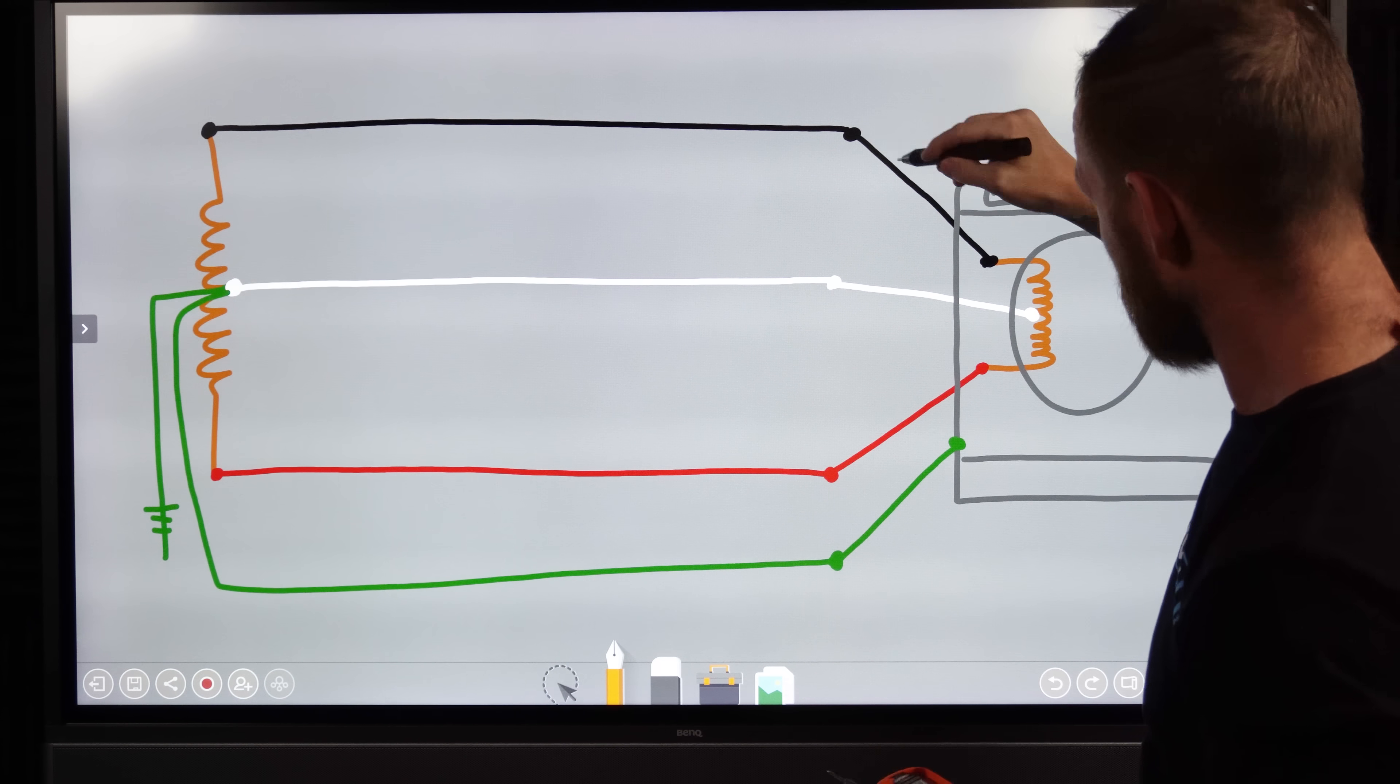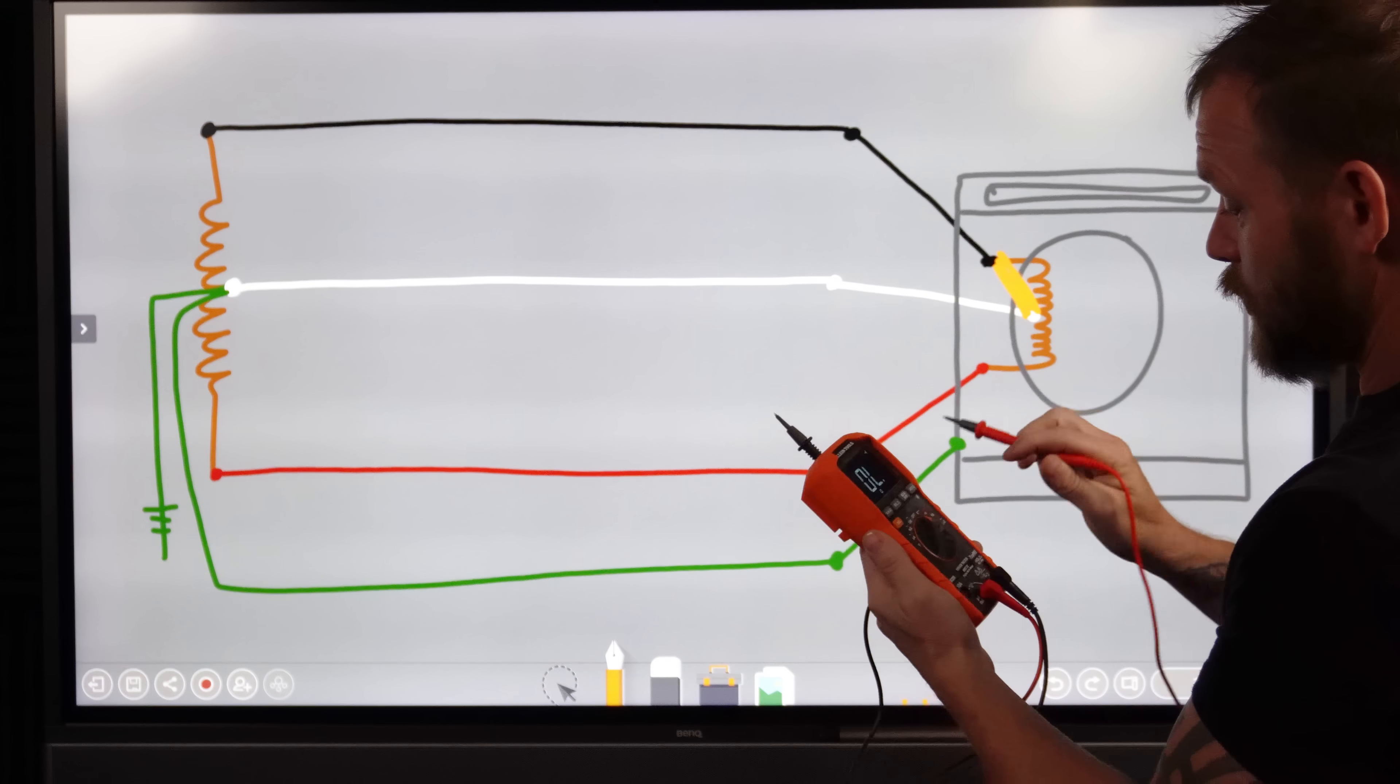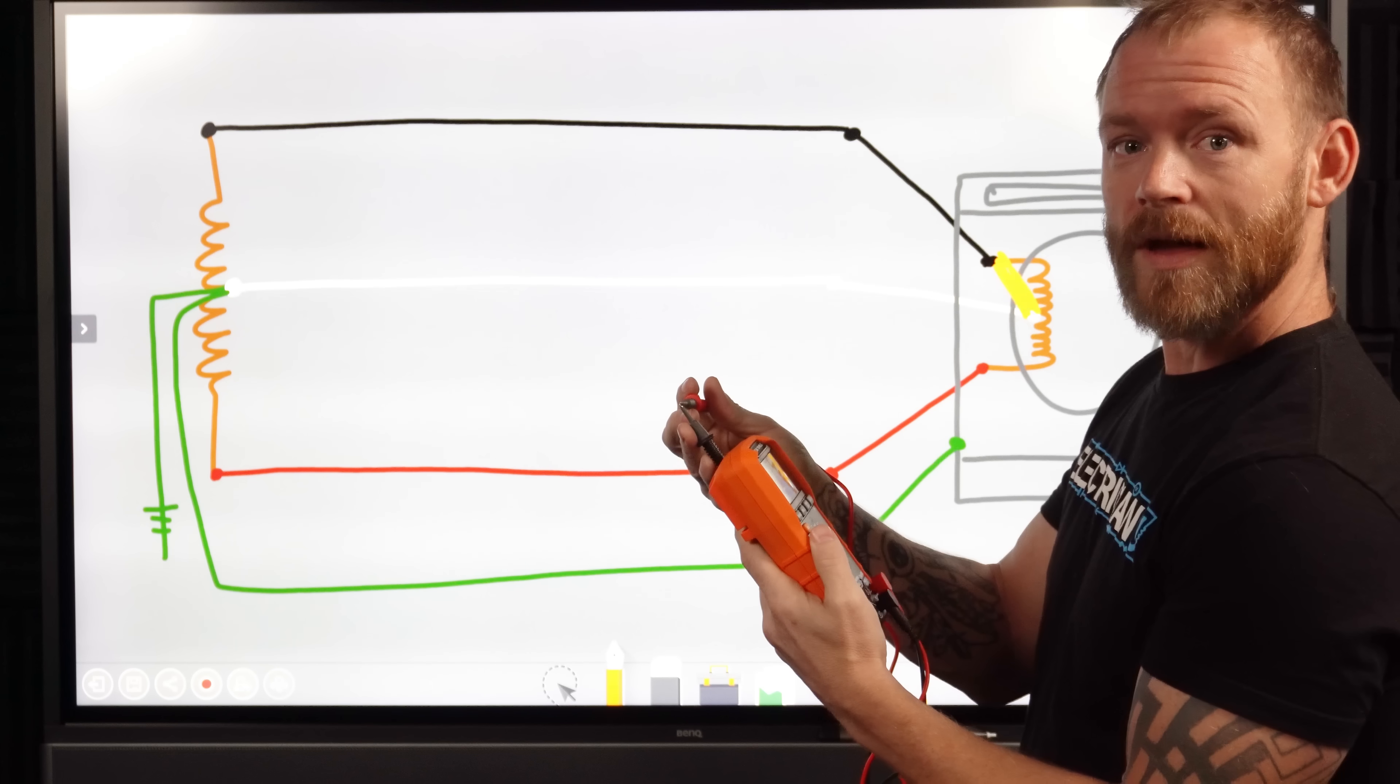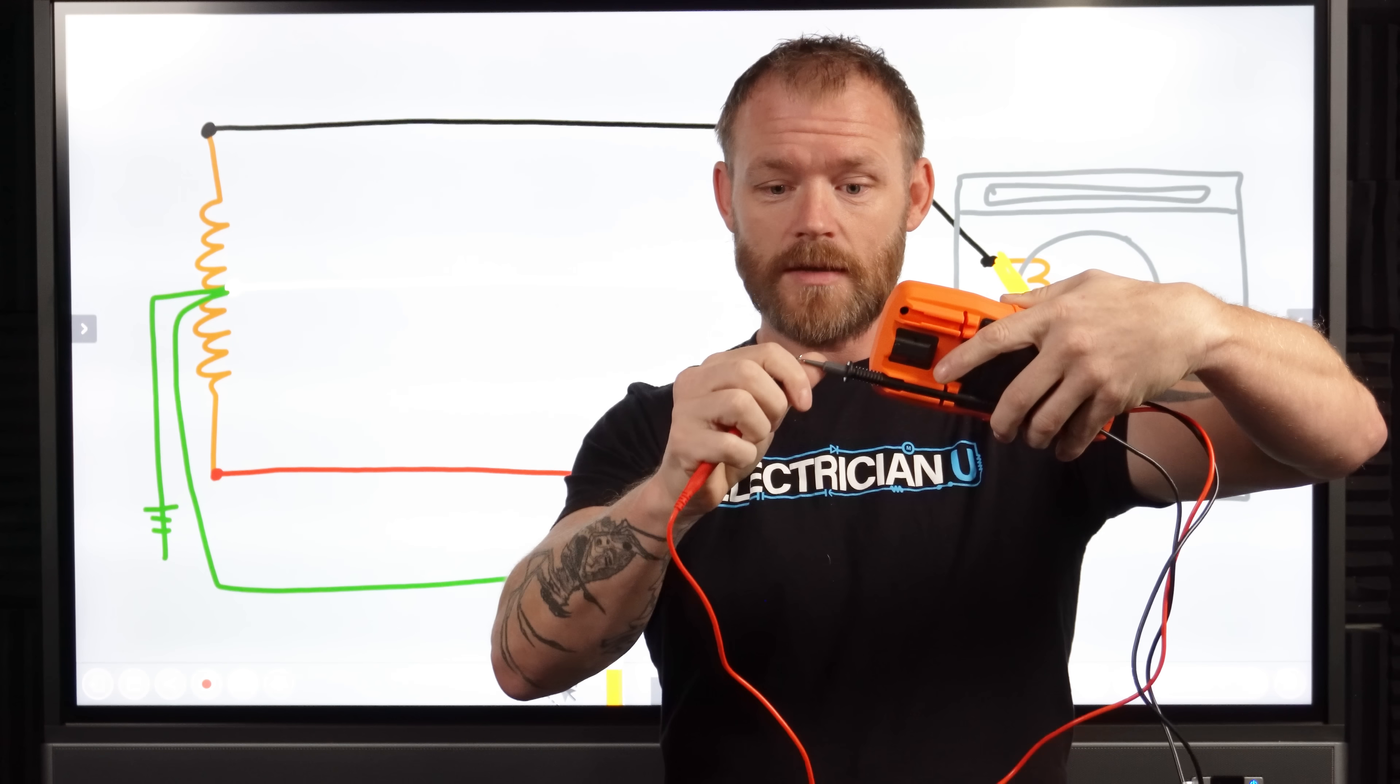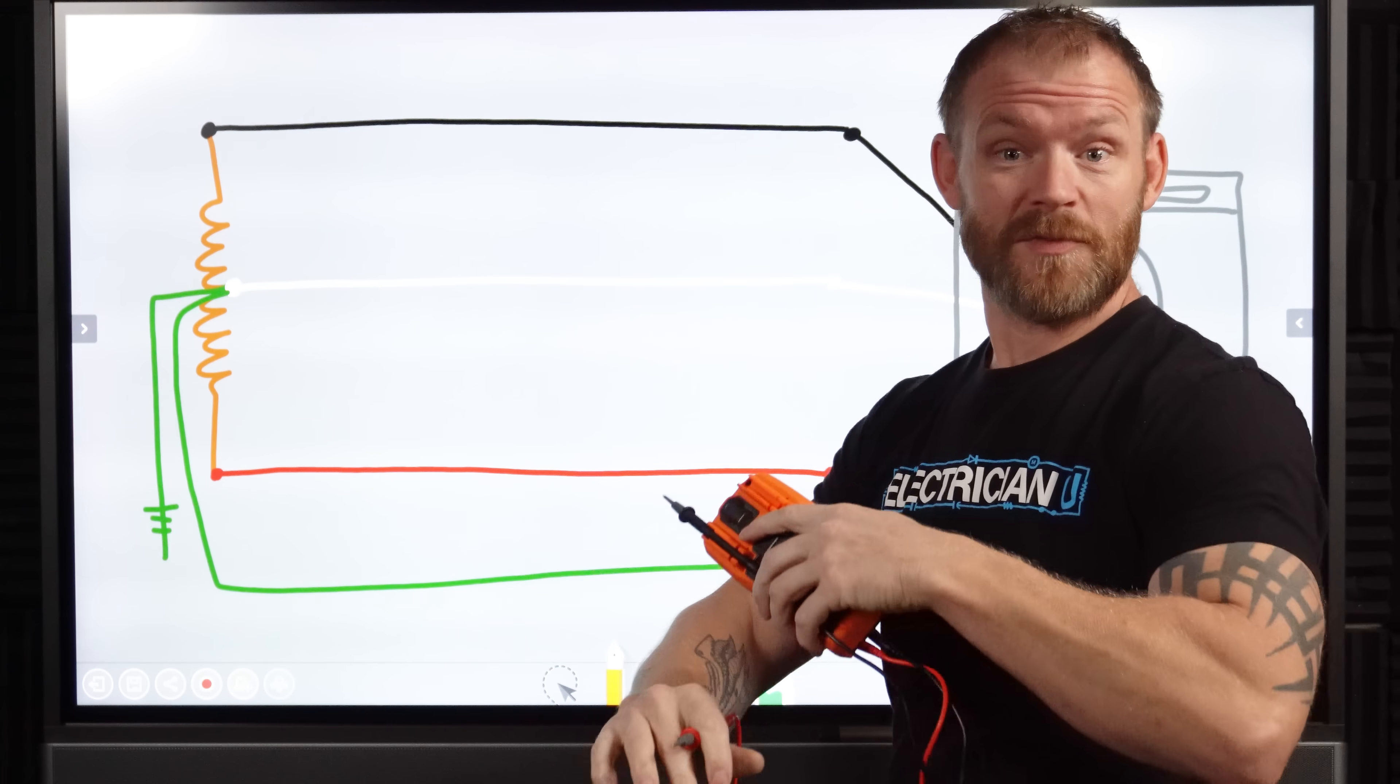So I've got a short circuit over here. Let's do this again. Say for some reason, like these two wires are connected and these are not, what I'm going to do is I'm going to put my meter still on the Ohm setting, but I'm not looking for a resistance value. I'm just looking for continuity. When I touch the tips of these together, that tone right there shows me that I have, you can see that, a complete loop. Continuity testing always gives us a complete loop. If it doesn't make a sound, then the loop's not complete. So this is a useful tool. I use this all the time for tons of different things.